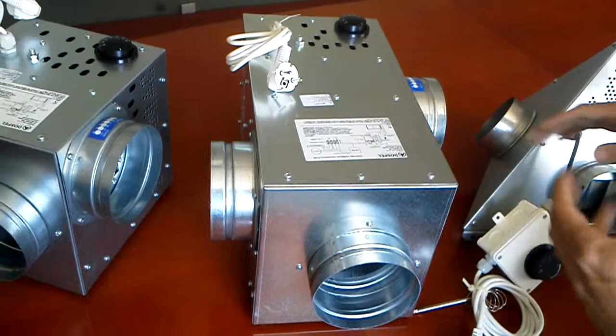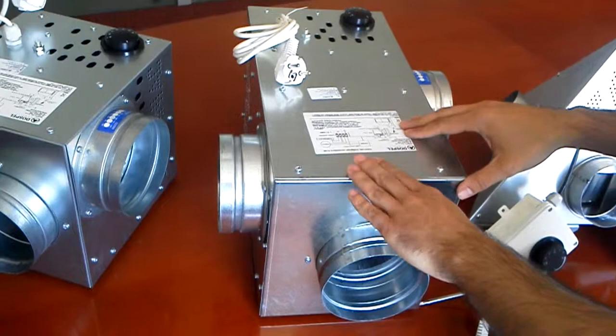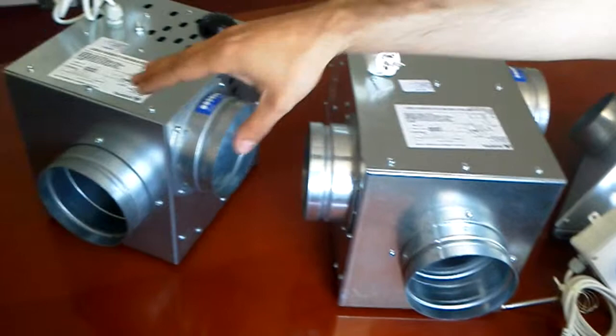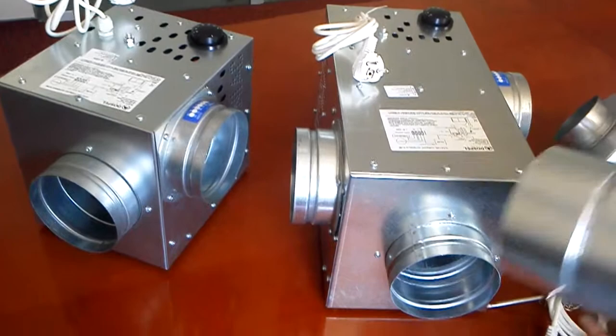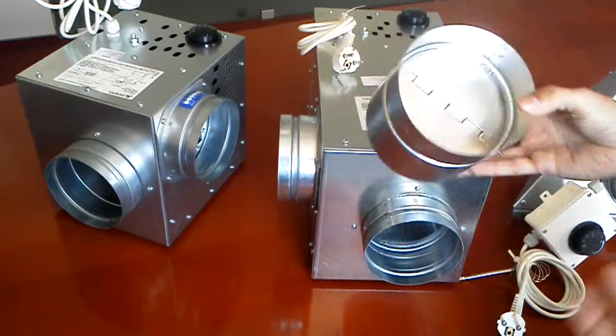So basically this protection means that if the device gets too hot, instead of air being forced through here, the air is also circulated through this tube here, which allows to stop the device from overheating. Also another layer of protection is this damper. As you can see, it closes to stop or dampen the airflow.